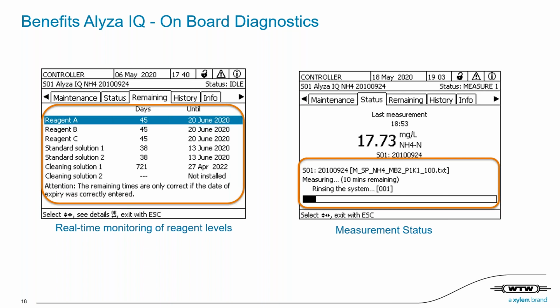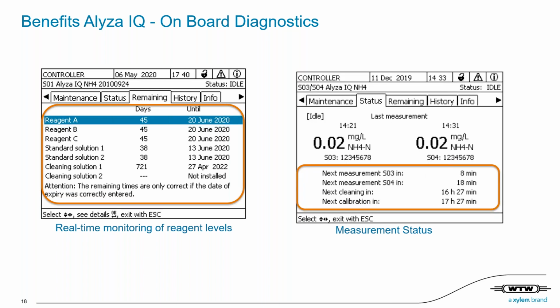So the current stage is the measurement cycle where 10 minutes are remaining. So it just started with a measurement and it's currently rinsing the system for preparation of measurement. In addition, as you can see in the next screenshot, the display shows during waiting mode the next process stages and when they will take place. For example, in that case, the next measurement is in 8 minutes for channel 1, in 18 minutes for channel 2, and calibration and cleaning is more than 16 hours away.